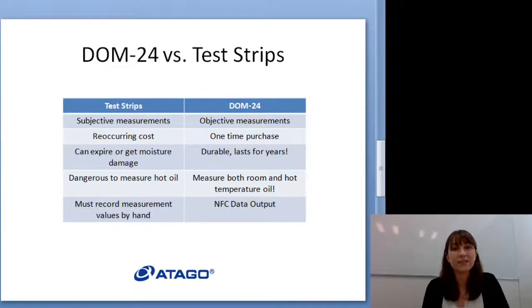There are some other ways to check the oil, like sending samples to a third-party lab for some more extensive testing. Some people just look at the oil and think, oh, it's dark enough, or it's smelly, or there's stuff floating in it, so I'll change it. There are some other color comparison methods as well. I think I visited one customer that had a little vial of fresh oil, and they would take a little bit of the old oil and compare the two. If it was too dark, then they would change it. So that was interesting. But definitely, I think the easiest way that anybody can measure is with a digital oil meter like DOM-24.